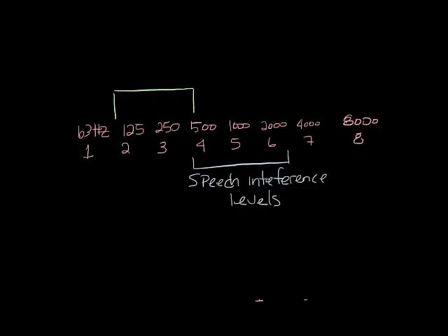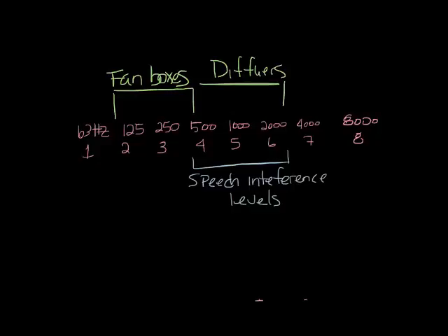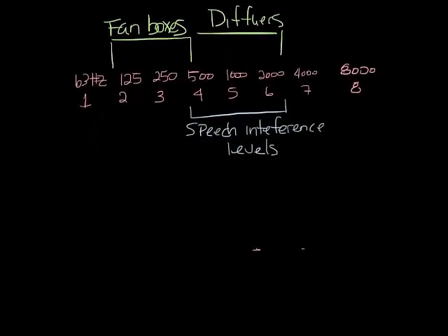Fan boxes, for instance, have their highest sound levels in the 2nd and 3rd band, while grills and diffusers create their highest sound level in the 4th, 5th, and 6th bands. You often see HVAC data shown in octave bands 2 through 7 only, because that's where the product's sound level peaks. But in room design, high decibels in the 1st and 8th octave bands can also cause problems. Okay, so let's scoot this out of the way a little bit.